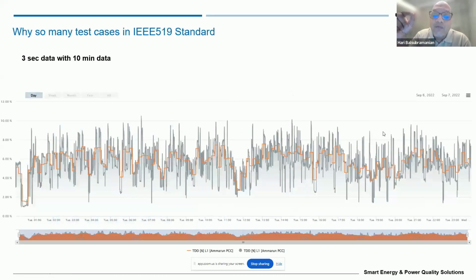Now, why we need to see 3-second and 10-minute data in IEEE 519 is the next question. You can see this graph where you have 10-minute values recorded for TDD, and 3-second values recorded for TDD in gray. The 3-second value is in gray and the orange one is the 10-minute value. As I said, the limits are different for 3-second values and for 10-minute values. So this gives a clear idea that if our voltage or the information is very much fluctuating, then the limits are high and we will still be in a position to follow.